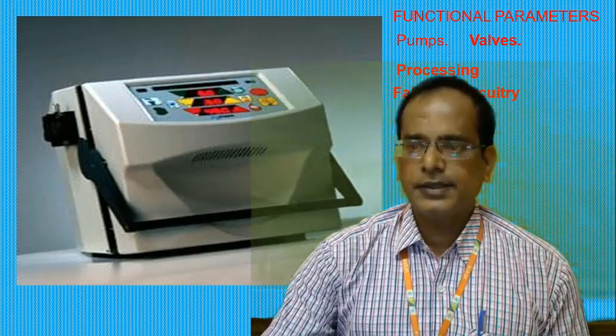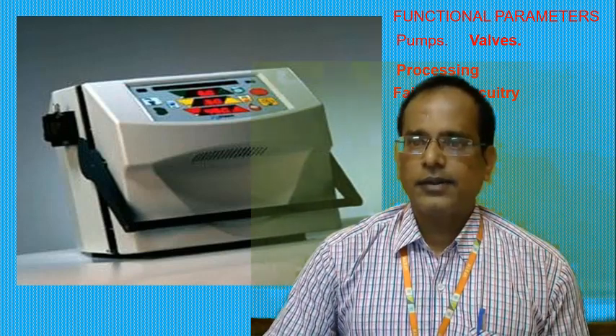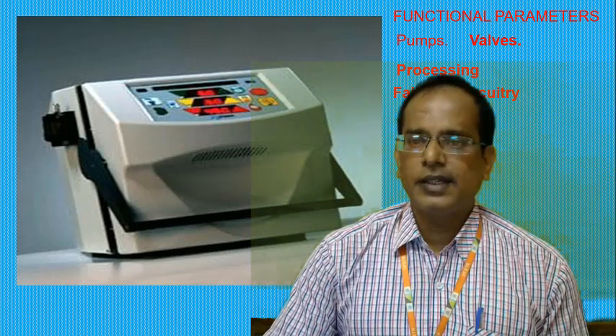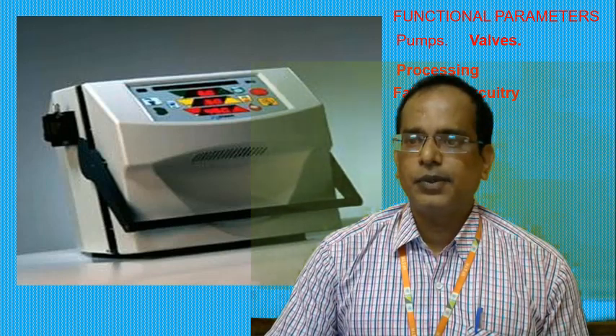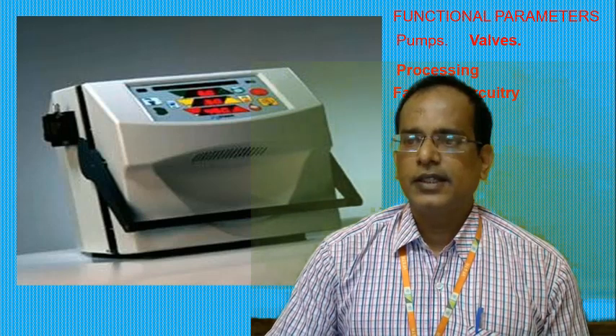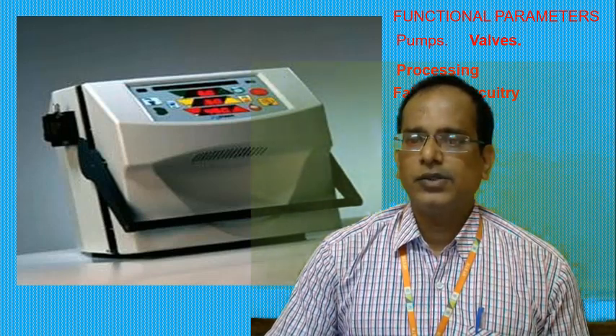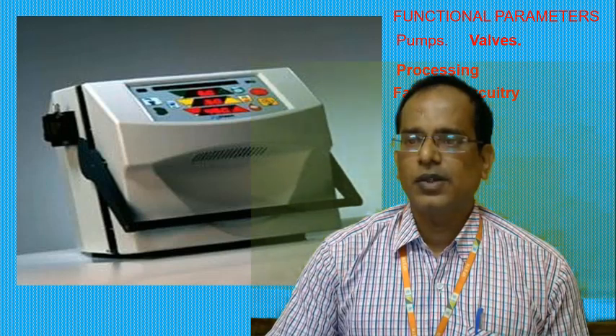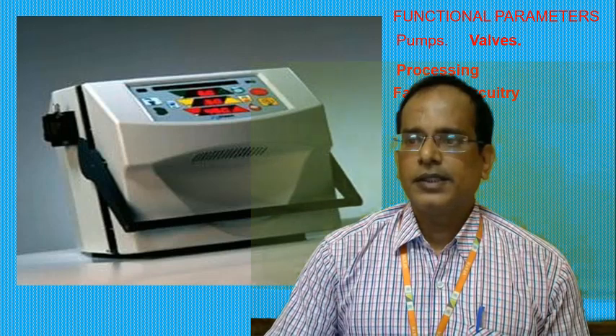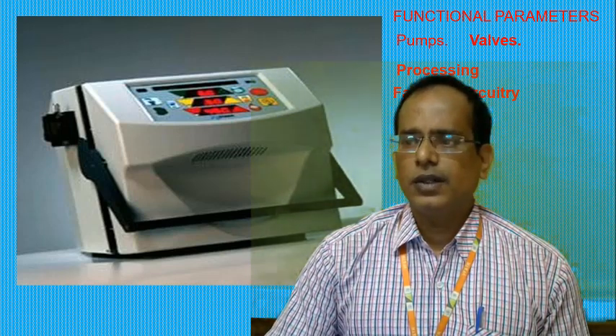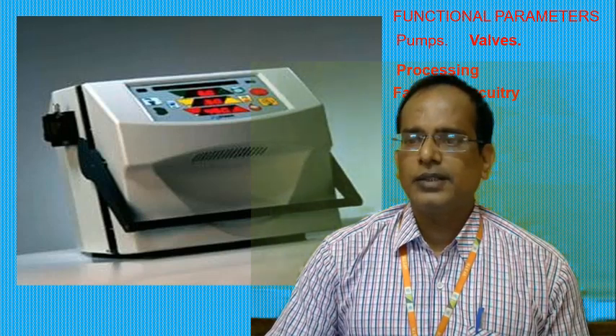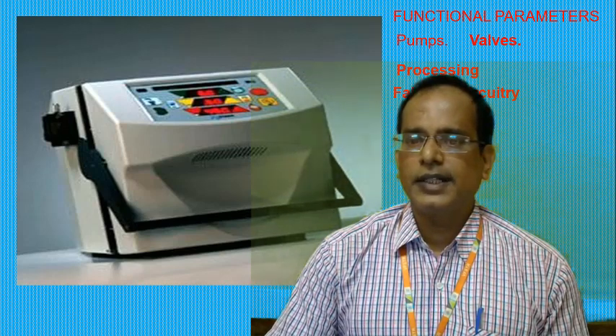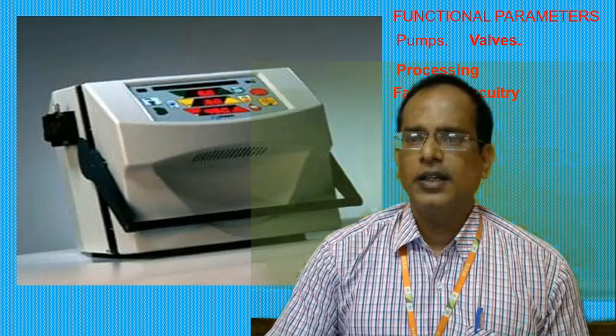The fourth functional parameter is fail-safe circuitry, which is very important in all machines. ICs with self-test and fault-reporting capabilities are very useful for maintaining patient safety under a single-fault condition. Additional monitoring circuitry is commonly used to monitor power supply voltages, while watchdog circuits ensure microprocessor operation remains within bounds. Both audible and visible alarms are provided to alert the user when a warning or fault condition occurs.